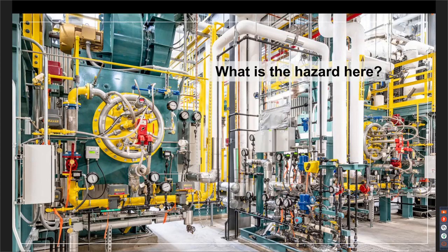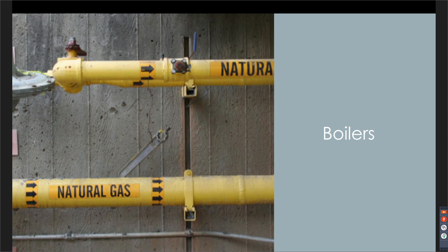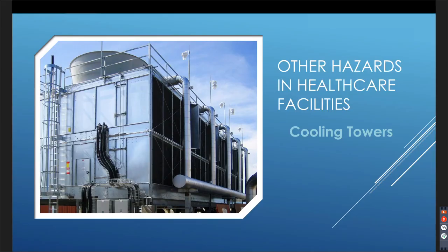Moving on to boilers, what's the real hazard with boilers? Well, they get pretty comprehensive, but really the real hazard with boilers is natural gas. And the natural gas needs to be installed in a manner that's consistent with the plumbing code and what the code allows. Above and beyond that, these aren't overly hazardous, assuming that the various pressure relief and temperature relief is available on these. Again, the piping needs to be adequately braced and adequately anchored, as we talked about earlier with somebody's really good question. But other than that, there are not a lot of special requirements.